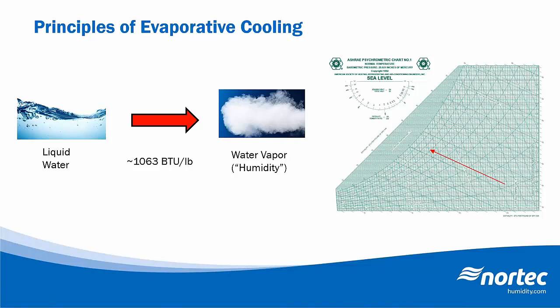So with an evaporative system, we're changing the sensible heat in the air to latent heat to evaporate that water. So this is a constant enthalpy process. So if we were to plot it on a psych chart, it would follow a line of constant enthalpy. Since the deviation between the enthalpy line and the wet bulb line is fairly small in most cases, you may sometimes hear this referred to as a constant wet bulb process. But because we're changing the sensible heat to latent heat, the air temperature drops and we get a cooling effect as well. So the only energy that we need to put into the system is the fan power required to move the air and the power to move the water. So that means for every pound of water that we're evaporating, we can achieve about 0.31 kilowatt hours of free cooling with these types of systems.